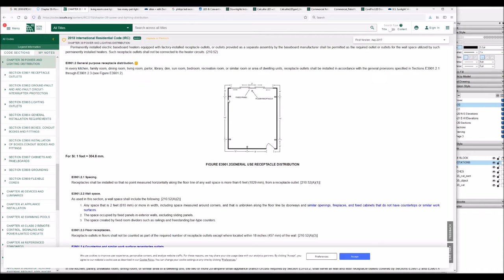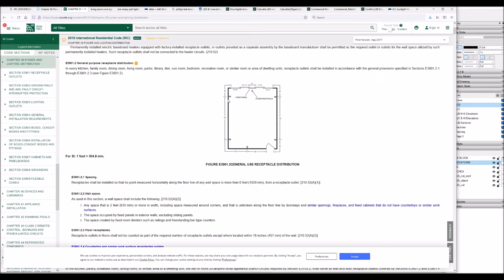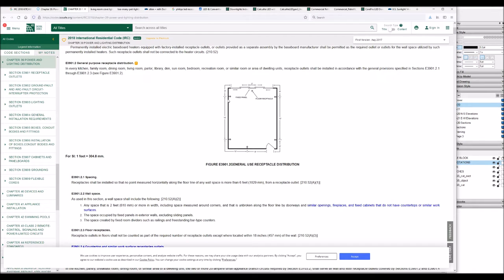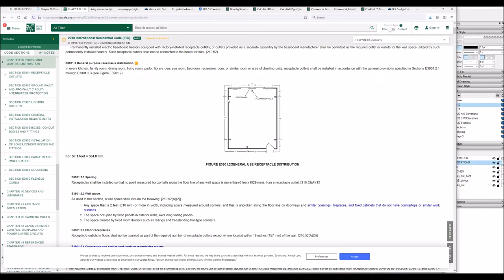My general rule of thumb is at least every 12 feet, put a plug and then put at least one in every wall. So a small bedroom will typically have three walls with a plug in each wall and the fourth wall will be mostly taken up by a closet and door. If it's a medium-sized bedroom, you can expect more. And for a large bedroom, you should really place them where you think they're most needed based on what furniture arrangements you expect to see, keeping in mind a 12-foot maximum distance.